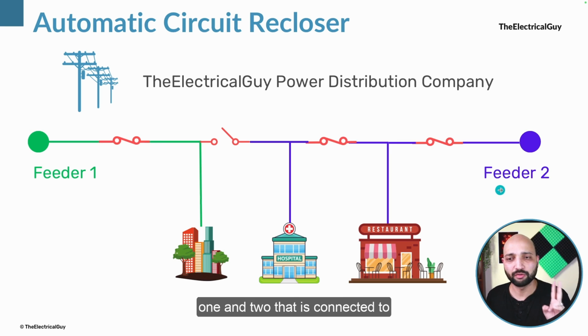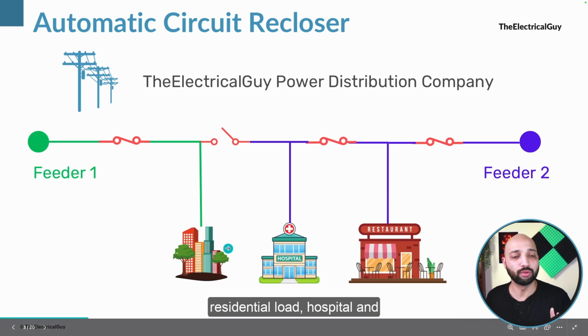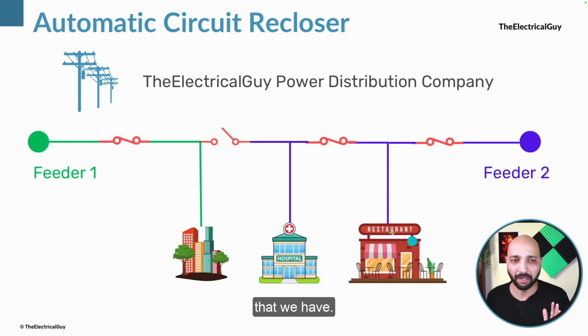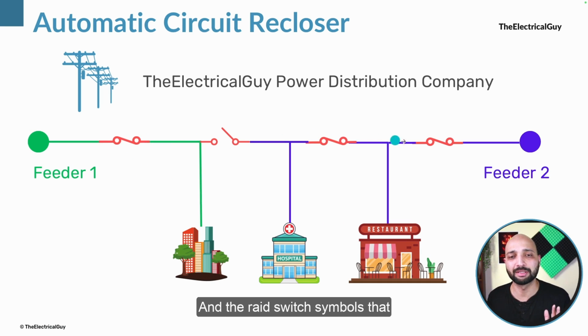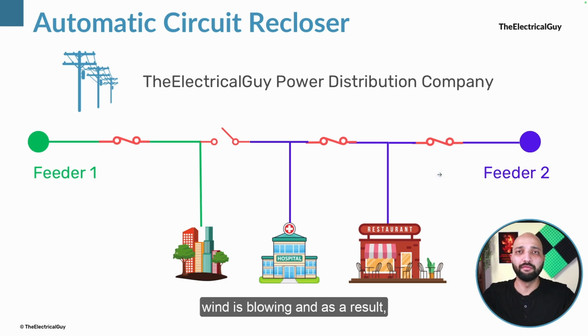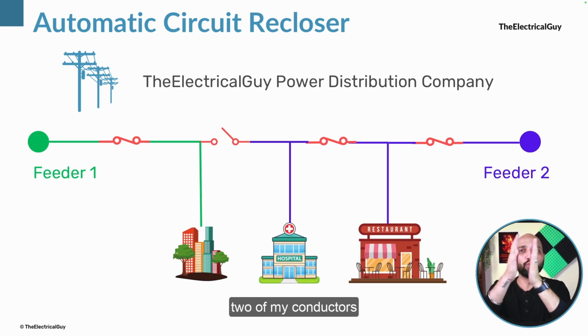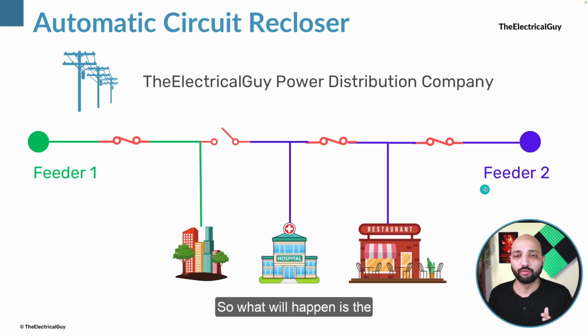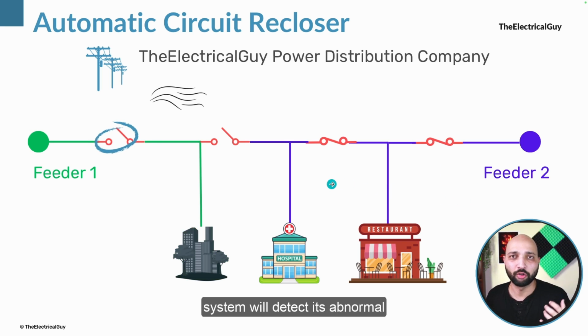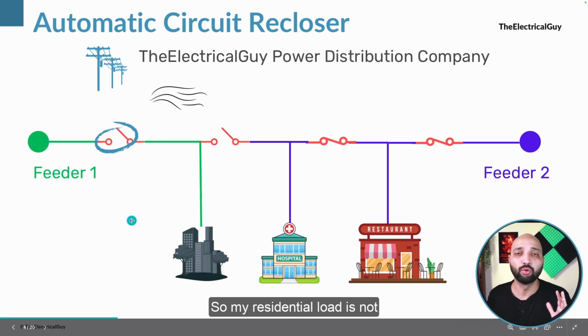So we have two feeders, 1 and 2, connected to a residential load, a hospital and also commercial buildings. The red switch symbols that you see here represent the circuit breakers that I have installed. Now imagine a very high speed wind is blowing and as a result two of my conductors stick together. The system will detect this abnormal situation and this circuit breaker will open here. So my residential load is not getting power anymore, right?